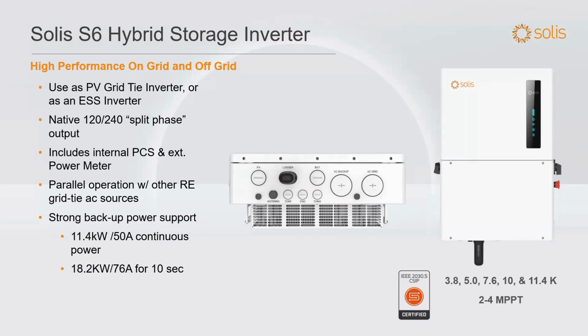76 amps is quite a bit of amps, and it can start some of these smaller 2.5, 3-ton air conditioners. But when you get into 5-ton air conditioners, and you'll sometimes see this on these massive homes in the U.S. and I suppose Canada as well, right? In Toronto, Vancouver, these sorts of things. You see these massive homes with these 5-ton air conditioners, and they need a 100-amp start. Well, you can put soft starts and things like that on it, but you'll need a full 100 amps of capability if you really want to reliably start it. And so we're building towards that, actually, and these new transformerless inverters are really building up a capability there.